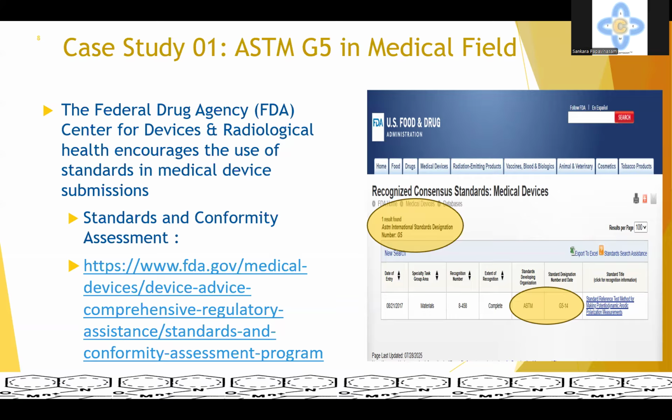So only those devices, materials, or laboratories that qualify themselves using the famous S curve are allowed to do testing in the medical field. And this has been well established and practiced, so much so that some of the laboratories that do testing in the medical field will do the ASTM G5 almost every week, the first day of every week. That is a kind of rigor enforced by the medical field.